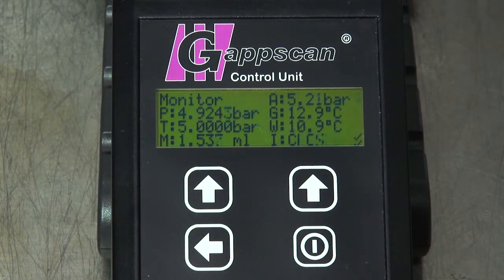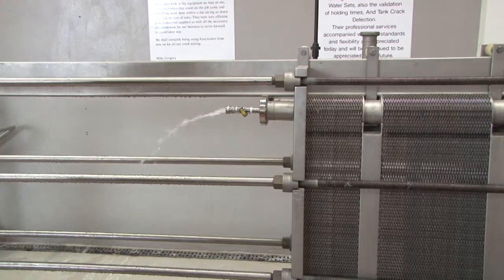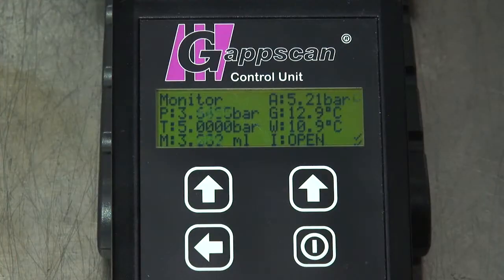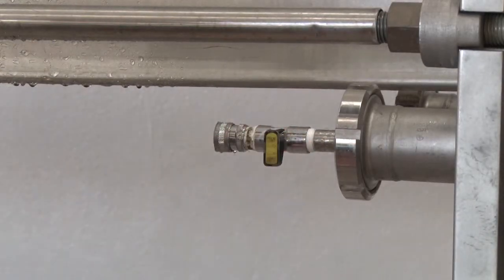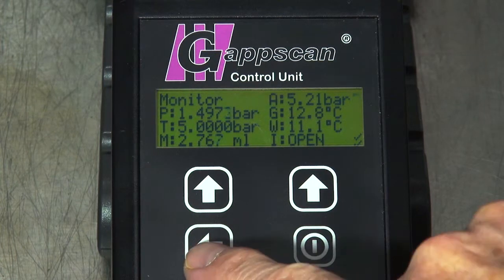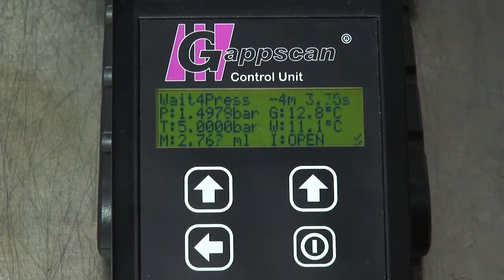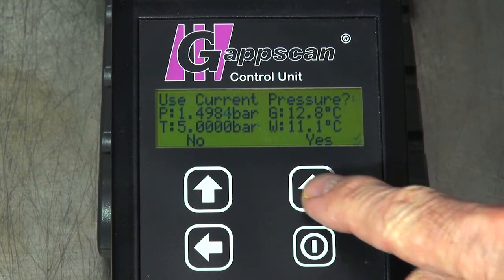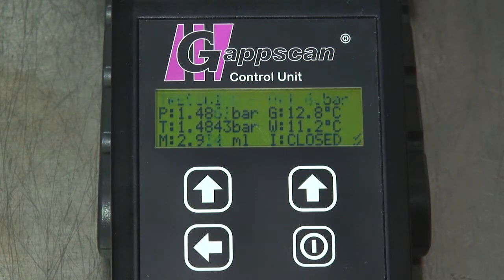Open the outlet valve on the heat exchanger to release water, which lowers the pressure. As P is approaching 1.5, reduce, then fully close the valve. Press the return key. Select Test. Press the I/O key. You will be asked if you want to use the current pressure. Select Yes. Once stabilised, the test will run automatically.